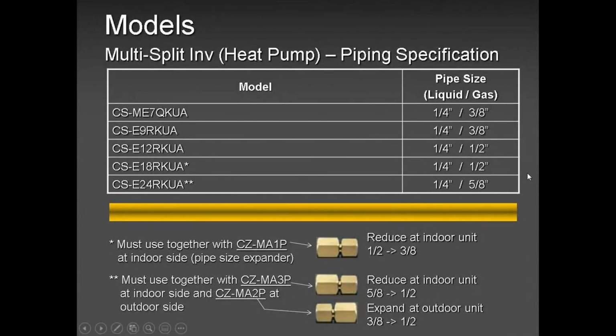So remember, for the 5-zone, guys, even though it's calling for 2 indoor units, you can't just pick any 2 indoor units. You have to maintain the minimum and maximum capacity. The minimum in this case is 4.5 times 3,412 BTUs. So if I picked 7,000, the unit would not work. It would throw me an error because I am not in that range. But if I put 12 and 12, I'm already past 4.5, so I'm good. Okay. So guys, please remember, a minimum of 2 indoor units on a multi-zone system.